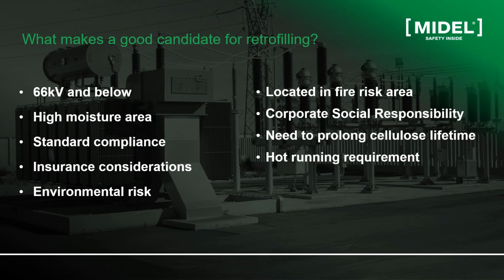Now, to summarize this section, transformers with voltage class lower than 66 kV are potential candidates for retrofilling, and so we can do an assessment on them or help you do the assessment, especially of the on-load tap changer and the paper condition, by taking a liquid sample. Retrofilling can be a good option for utilities if you have a high moisture problem in your transformers, always wet. Esters tolerate more moisture, and so you can reduce your maintenance periods, and so eventually save money. Sometimes the standards change, so you have to have a K-class fluid in a transformer to increase fire safety, and then retrofilling can offer you a solution either to meet the insurers or the environmental regulators.